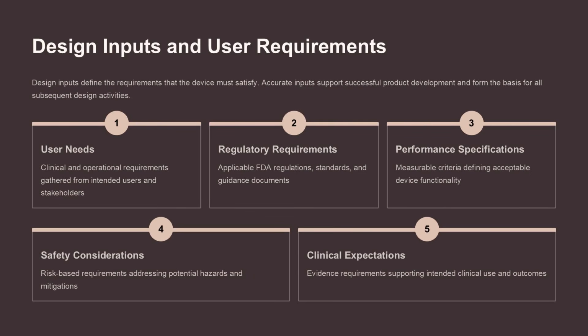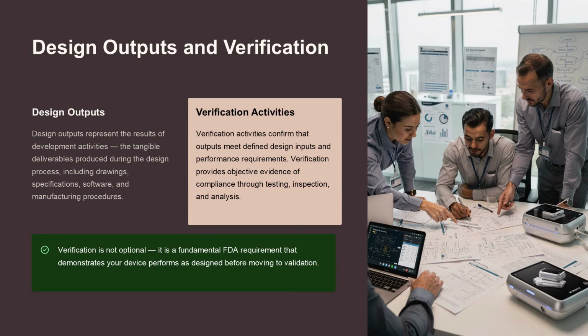Design inputs define the requirements that the device must satisfy. Accurate inputs support successful product development and form the basis for all subsequent design activities. They include clinical and operational requirements gathered from intended users and stakeholders, applicable FDA regulations, standards, and guidance documents, measurable criteria defining acceptable device functionality, risk-based requirements addressing potential hazards and mitigations, and evidence requirements supporting intended clinical use and outcomes.